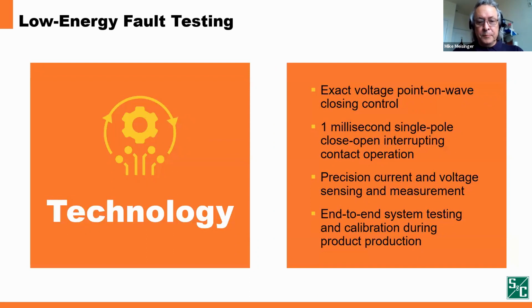Next slide, please, Kleber. How do we do this? Well, I always describe it as two parts of technology magic. One part of it is the electronics, and the other part of it is the mechanical. So we have to know exactly where we want to initiate a close open operation on the voltage point on wave and be consistent in that choice. Then we initiate this rapid close open operation. So the contacts are closed and open in 1 millisecond.